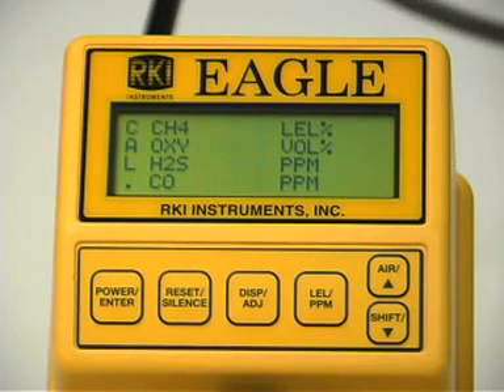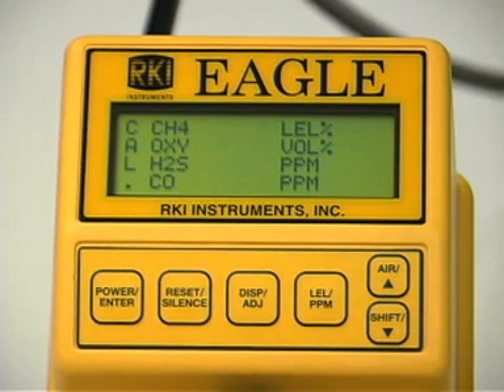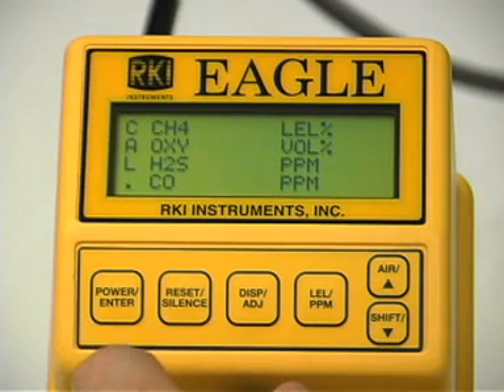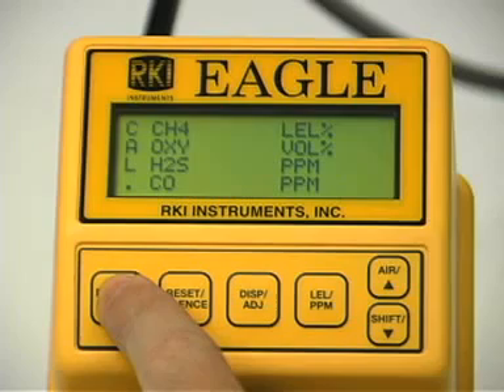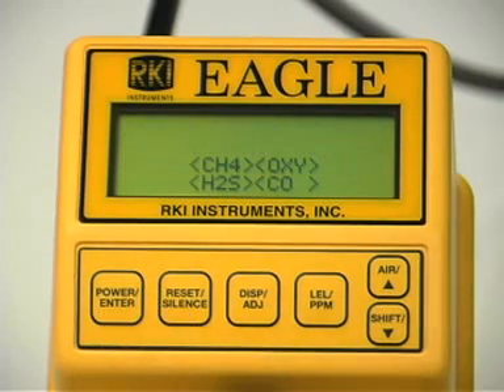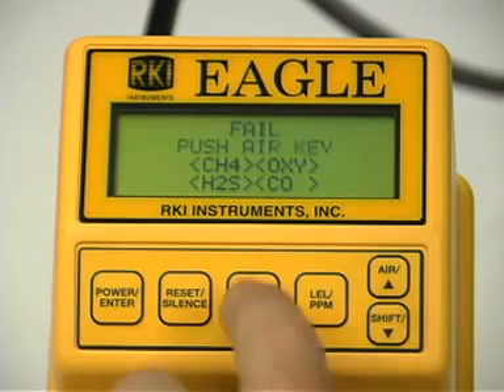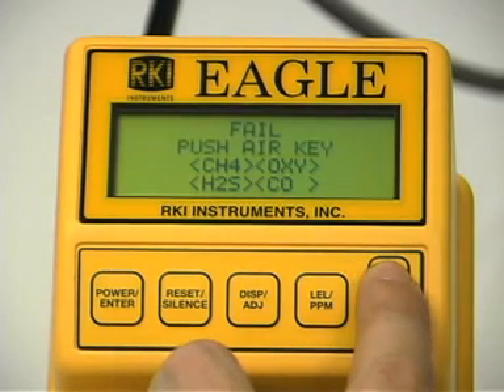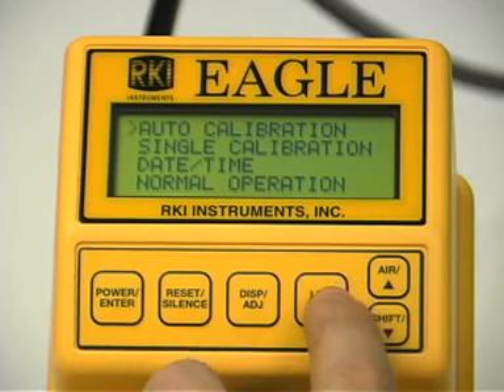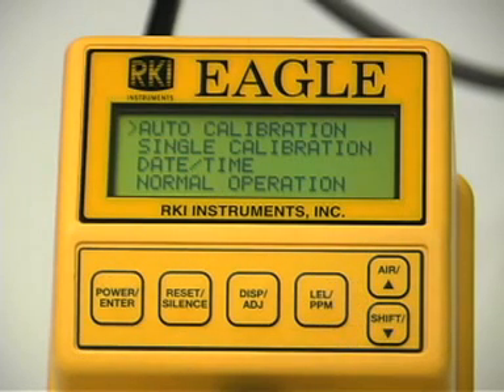If a sensor cannot calibrate to the proper value, the message Fail Push Air Key displays, and the Eagle lists the sensor that failed to calibrate. The sensors not listed as failed have calibrated normally. The buzzer and alarm lights will activate, so press the Up button to reset the alarm and return to the calibration menu.